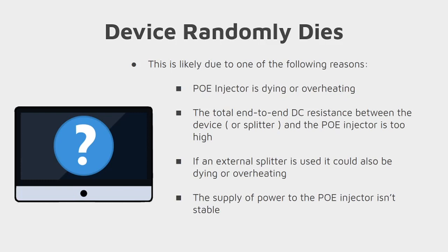Maybe even the maintenance department is testing a generator failover. And that's making it look like your device is randomly dying, but really it's just that the splitter is losing power for a split second, or maybe a couple seconds, and isn't allowing the device to come back on.